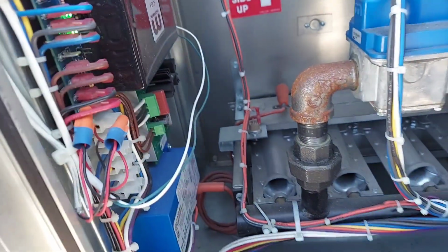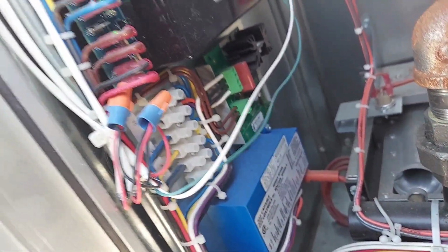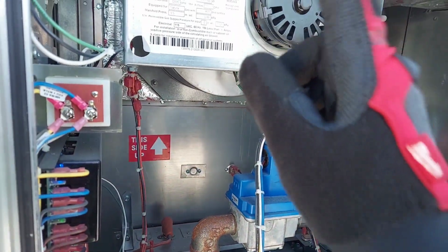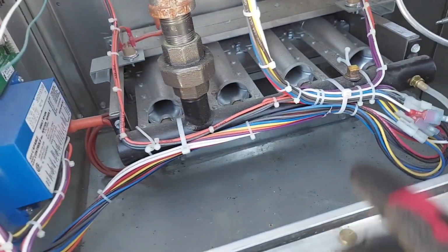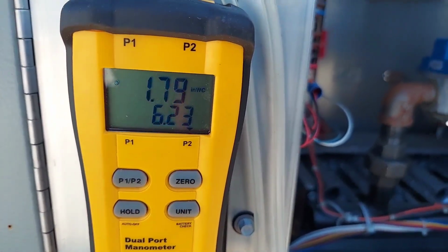I don't know, that sound of this one too, right? That humming, maybe that's the exhaust fan controller. But the exhaust fan, that's 2 stages as well. A low and a high speed. But let's look, we're at 1.7 low fire.